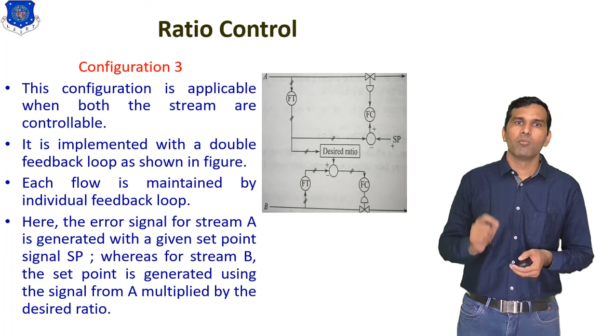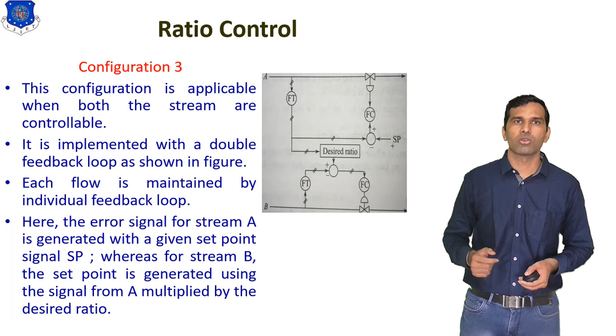Here each flow is maintained by an individual feedback loop. You can see in this figure each flow, the upper one and the lower one, is maintained by an individual feedback loop. Here the error signal for stream A is generated with a given set point SP, whereas for stream B the set point is generated using the signal from A multiplied by a desired ratio. So this is configuration 3 of the ratio controller.